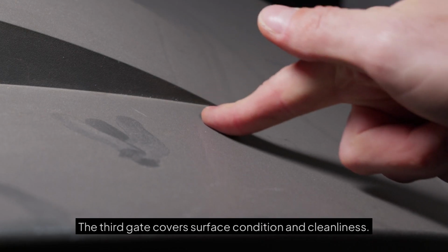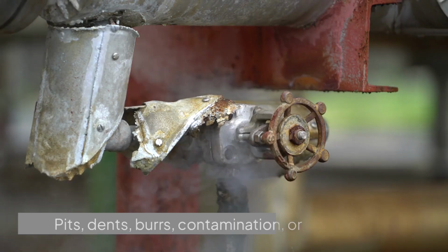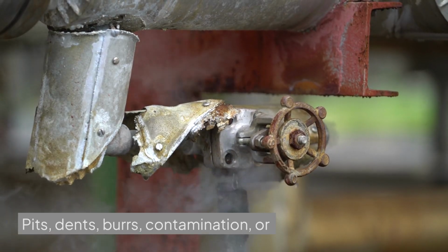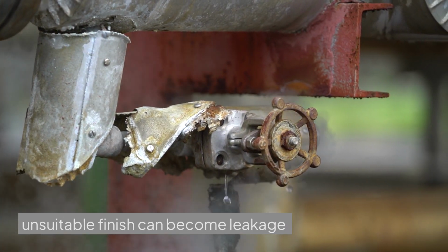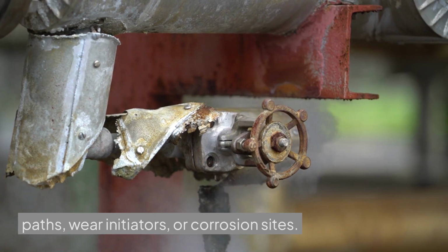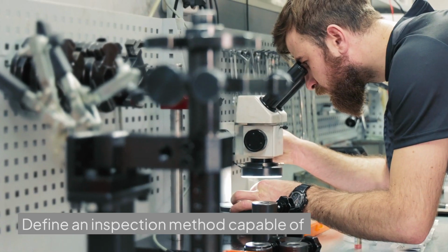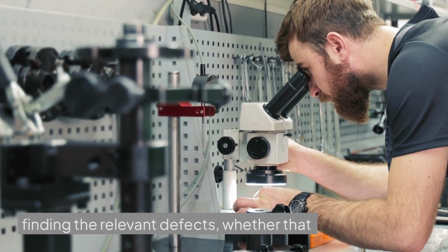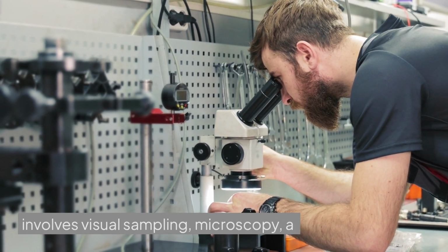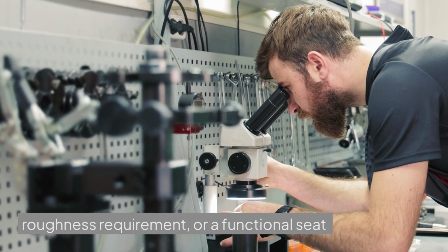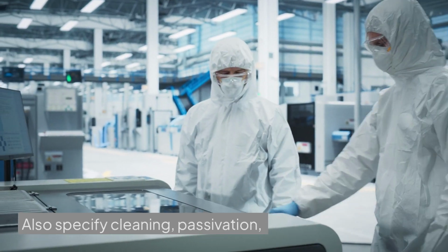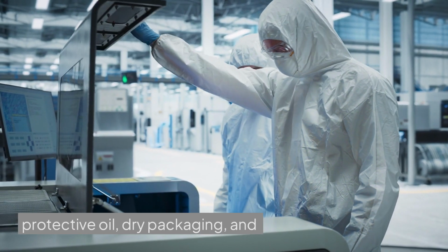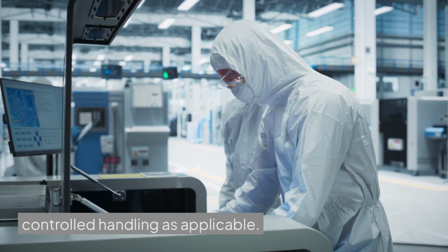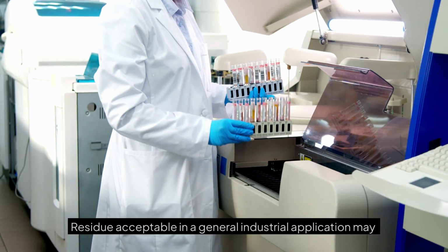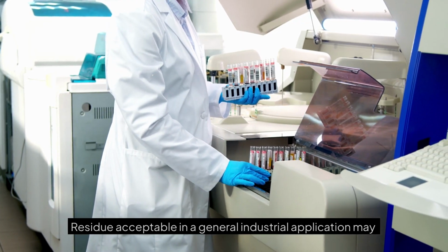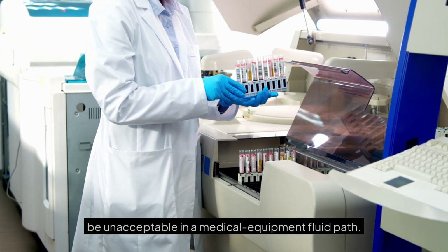The third gate covers surface condition and cleanliness. Pits, dents, burrs, contamination, or unsuitable finish can become leakage paths, initiators, or corrosion sites. Define an inspection method capable of finding the relevant defects, whether that involves visual sampling, microscopy, a roughness requirement, or a functional seat test. Also specify cleaning, passivation, protective oil, dry packaging, and controlled handling as applicable. Residue acceptable in a general industrial application may be unacceptable in a medical equipment fluid path.